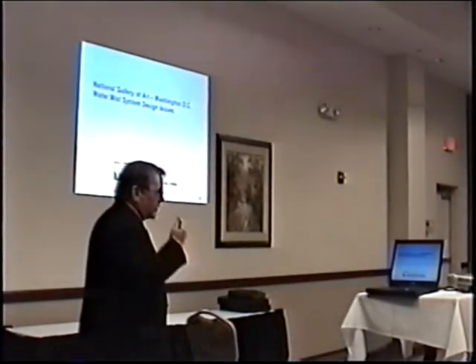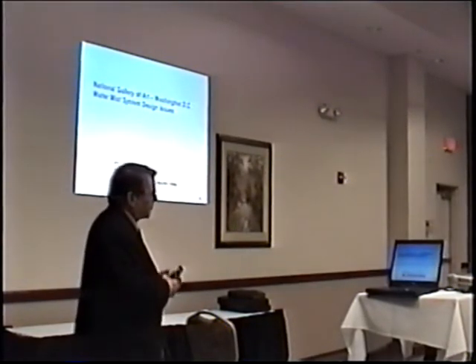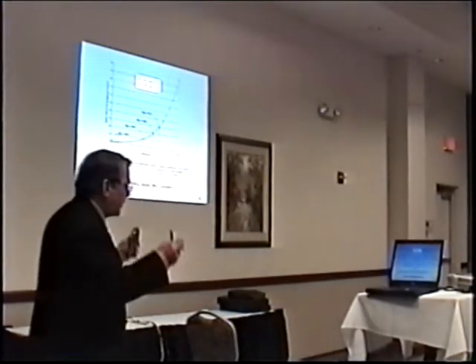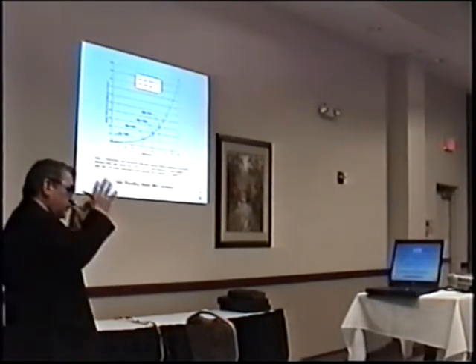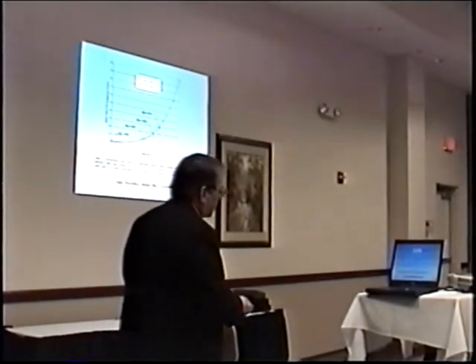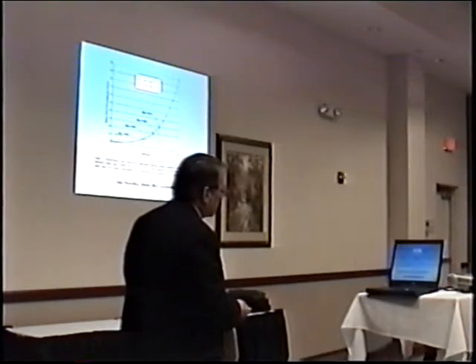same cycling operation. Well, what happens when you get into a larger volume space, when you're trying to work with a total flooding water mist system, where you depend on the enclosure to trap the heat, and for the fire to consume some oxygen, and for the heat to evaporate the water droplets and create water vapor. As you raise the temperature of the compartment, you raise the amount of water saturation that can be in water vapor phase, and your oxygen concentration comes down.